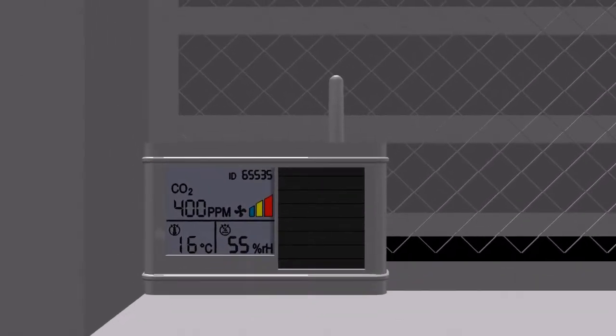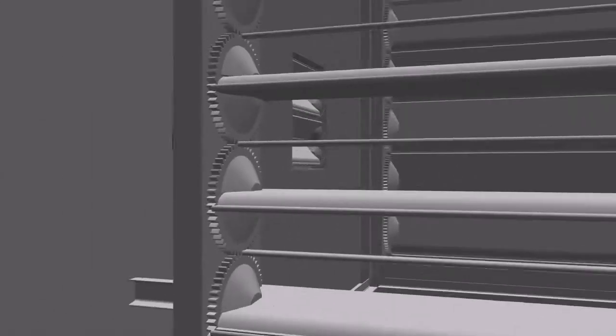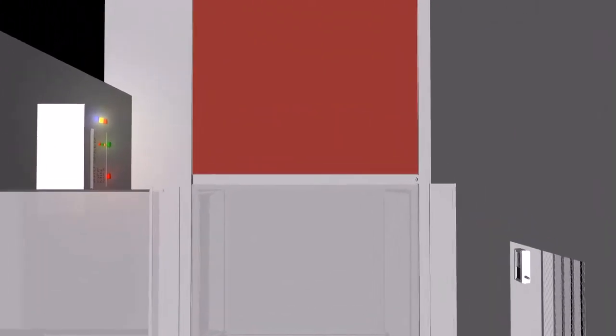Early morning, a wire-free solar IQ controller is installed for air quality measurement at fresh air intake. As you can see, fresh air is cooler, thus the air handler is set to free cooling mode by the IQ controller. This will allow complete fresh air to be supplied to the office spaces through the supply air ductwork and exhausted through the return air ductwork.